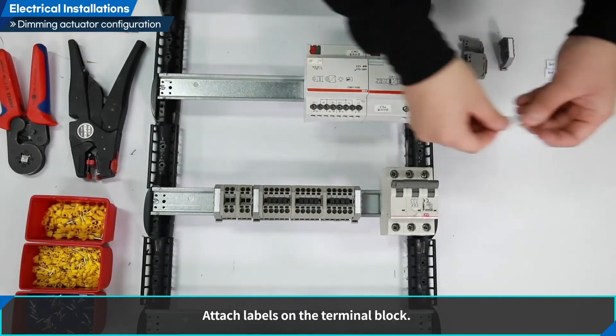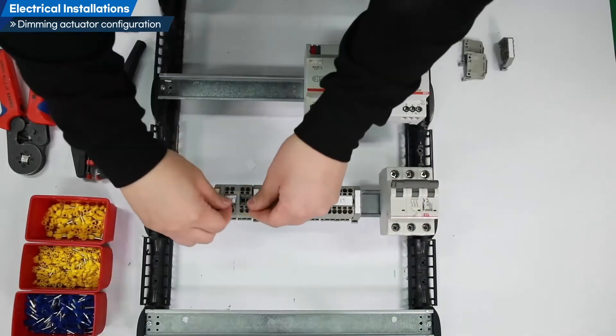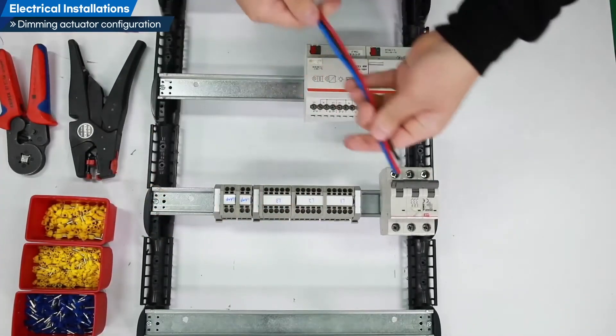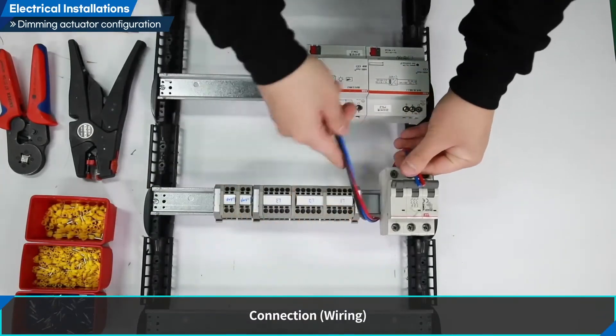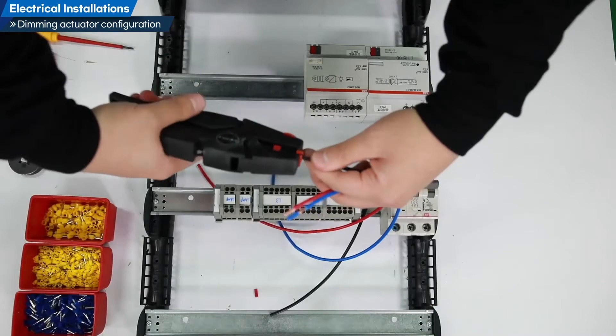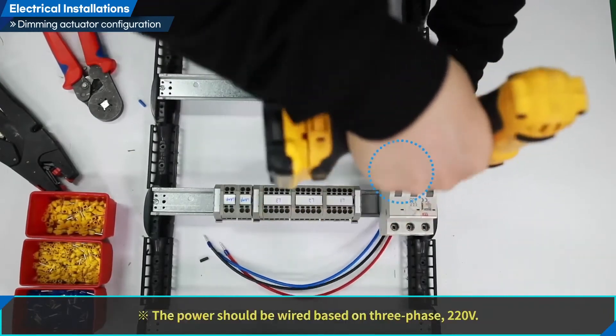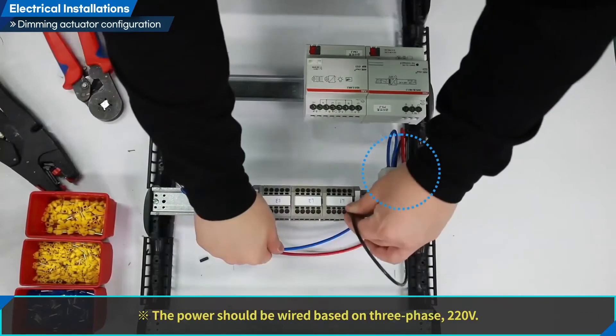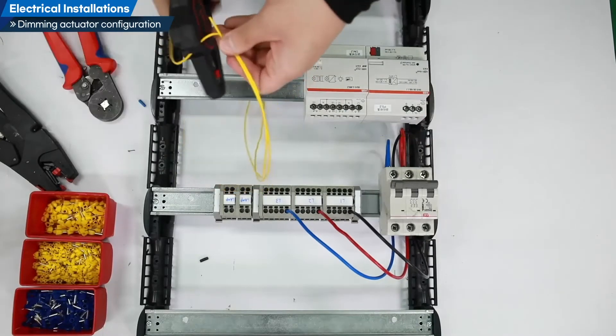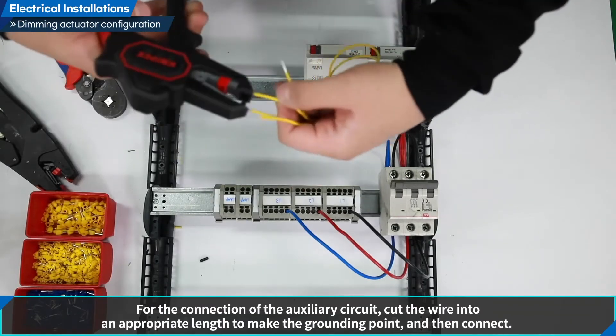Attach labels on the terminal block. Cut the main circuit wire into an appropriate length to make the grounding point. Connect the main circuit wire to the circuit breaker and the terminal block. The power should be wired based on three-phase 220 volts. For the connection of the auxiliary circuit, cut the wire into an appropriate length to make the grounding point and then connect.